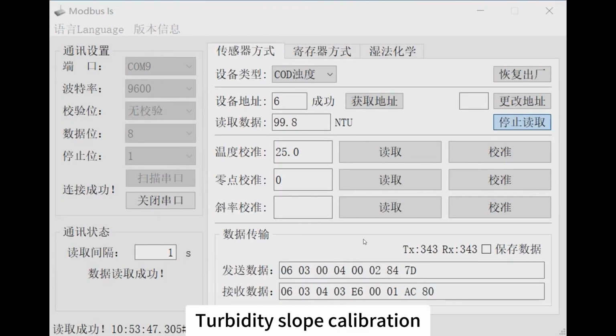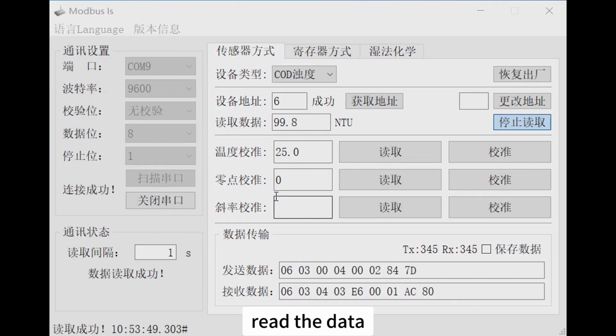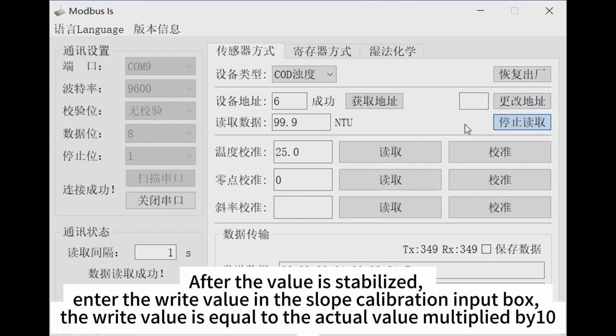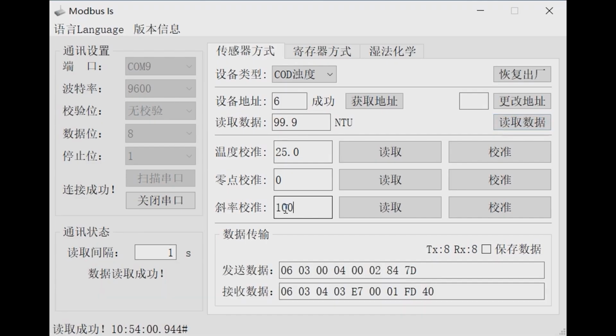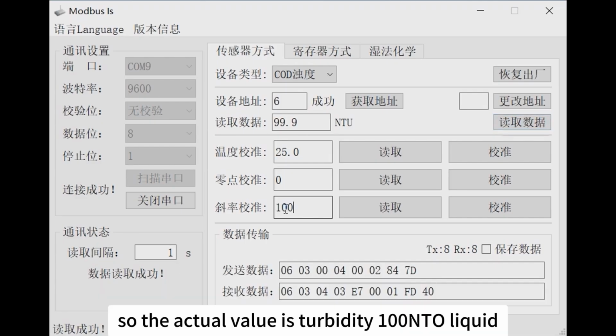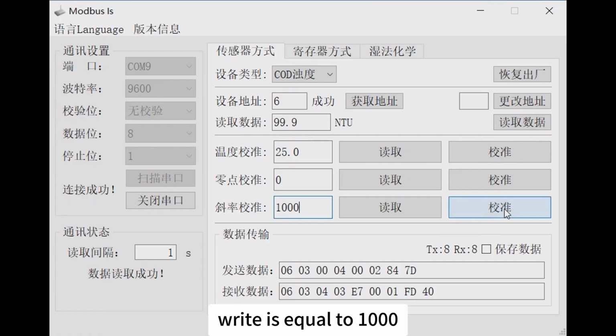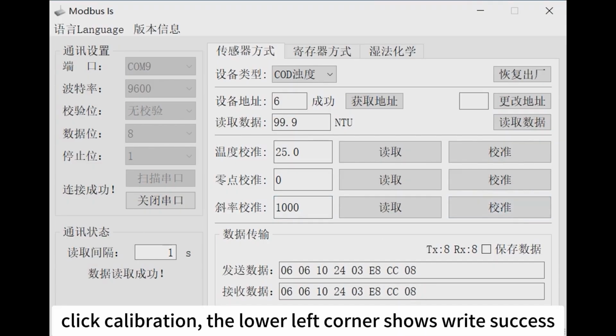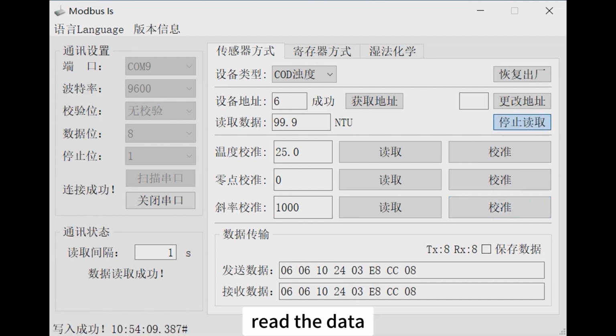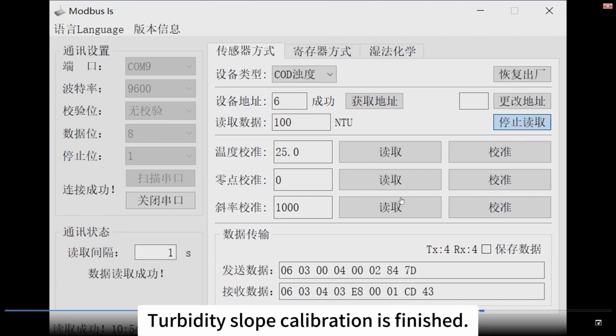Turbidity slope calibration. Read the data. After the value is stabilized, enter the write value in the slope calibration input box. The write value is equal to the actual value multiplied by 10. So the actual value is turbidity 100 NTU liquid, write is equal to 1000. Click Calibration. The lower left corner shows write success. Read the data. Turbidity slope calibration is finished.